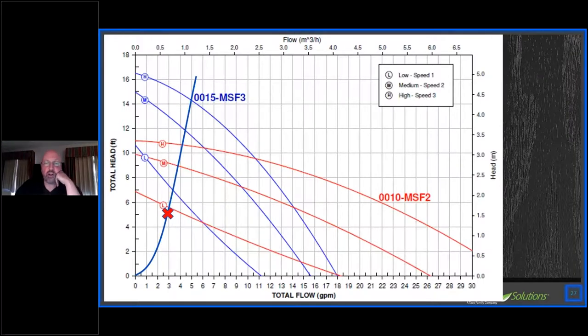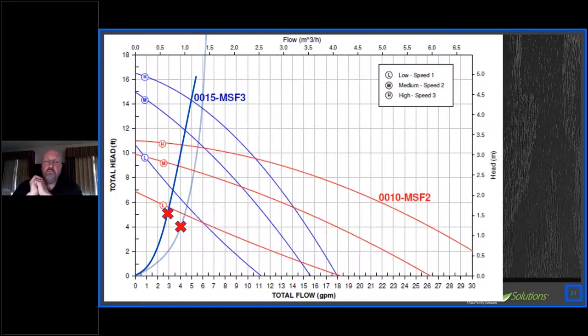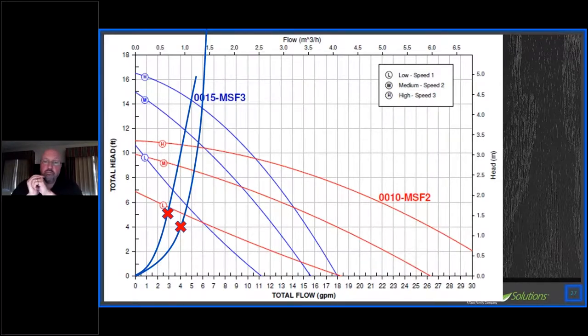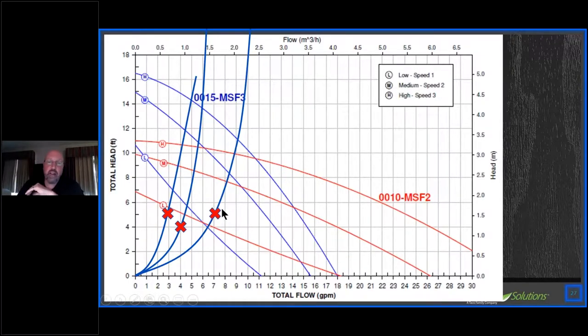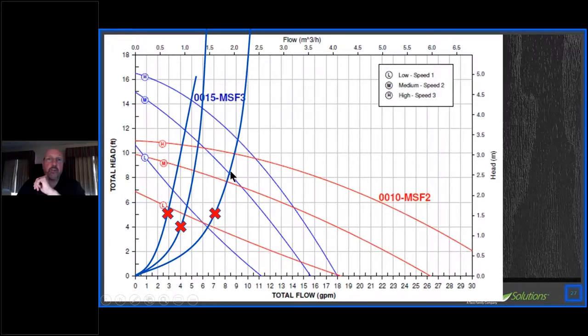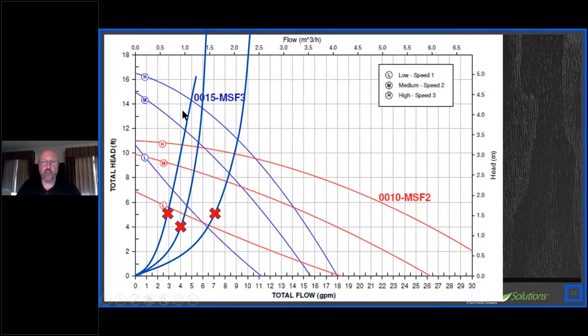Looking at three-speed circulators like the 0015 or 0010 three-speed: zone one at 2.8 GPM at 5.12 ft runs on low. Zone two at 4 GPM at 4 ft — on a zone pump system — also runs on low. Combined at 6.7 GPM at 5.12 ft, you're just above low speed. Because we likely overestimated head loss, this two-zone system could realistically run on low the whole time — or medium at worst.